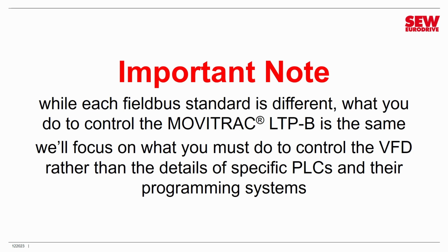What you send over the field bus to the VFD, commanding it to operate, telling it what speed to turn, these things are the same. They're independent of the field bus. So we're going to focus on that side of things: what you actually send to the VFD, and what you interpret coming back from it.